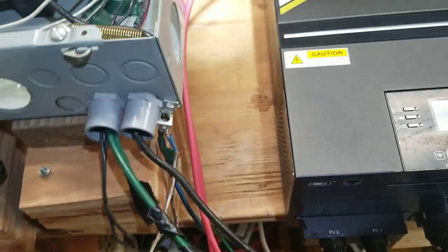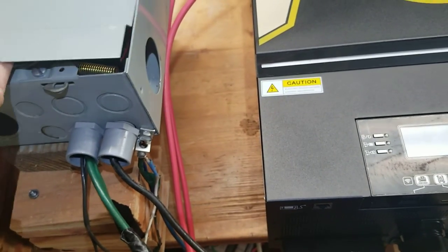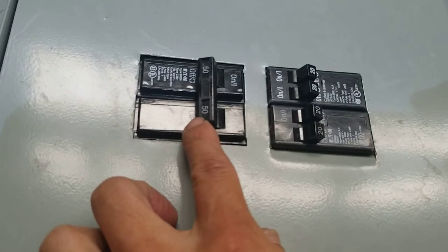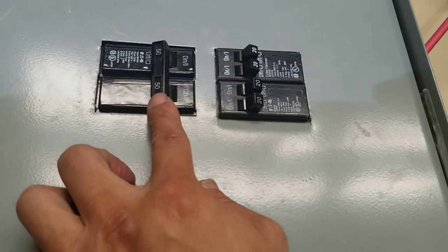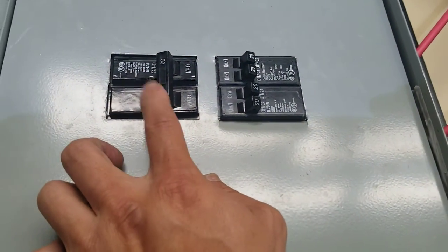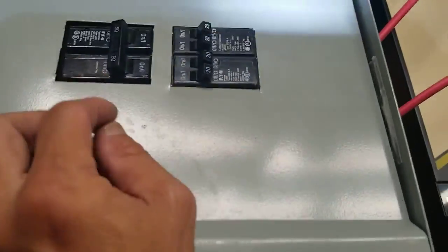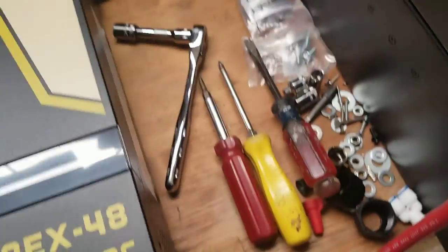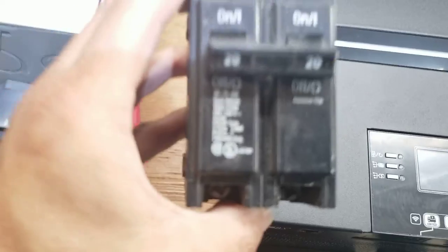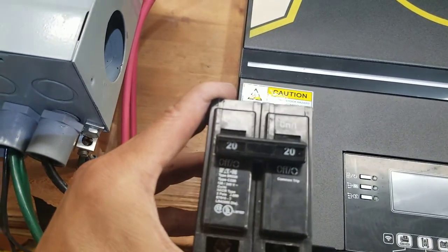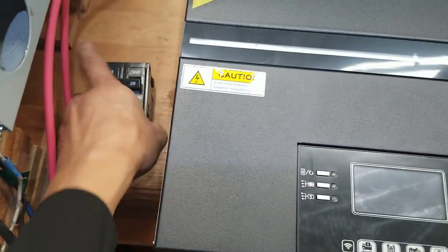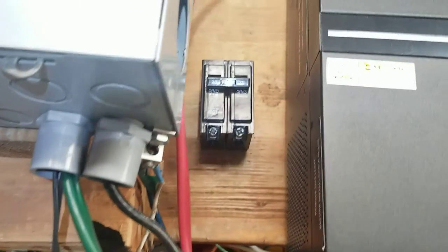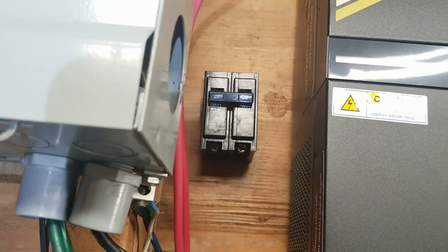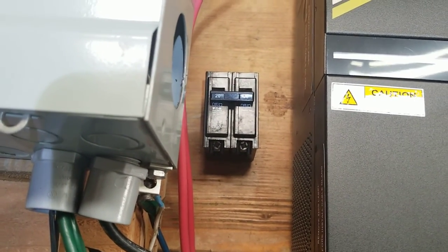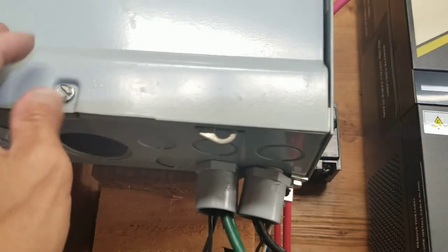Let me cover this up and then we can fire it up. See, now it's the 50 amp. Now if you use a Growatt inverter, you only use a 20 amp breaker—double pole 20 amp breaker for the Growatt inverter, because the Growatt inverter can only make a maximum of 22 point something amp, about 22 amp.